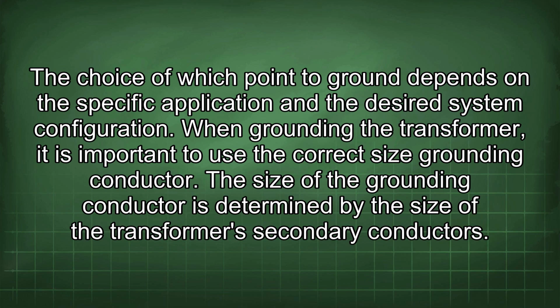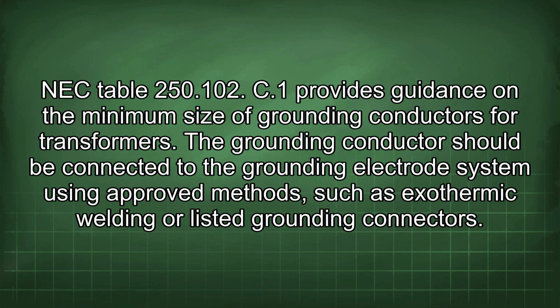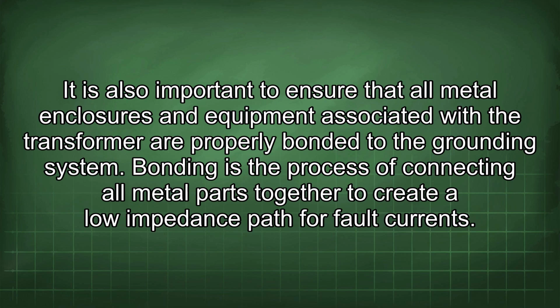When grounding the transformer, it is important to use the correct size grounding conductor. The size of the grounding conductor is determined by the size of the transformer's secondary conductors. NEC Table 250.102(C)(1) provides guidance on the minimum size of grounding conductors for transformers. The grounding conductor should be connected to the grounding electrode system using approved methods such as exothermic welding or listed grounding connectors. It is also important to ensure that all metal enclosures and equipment associated with the transformer are properly bonded to the grounding system.